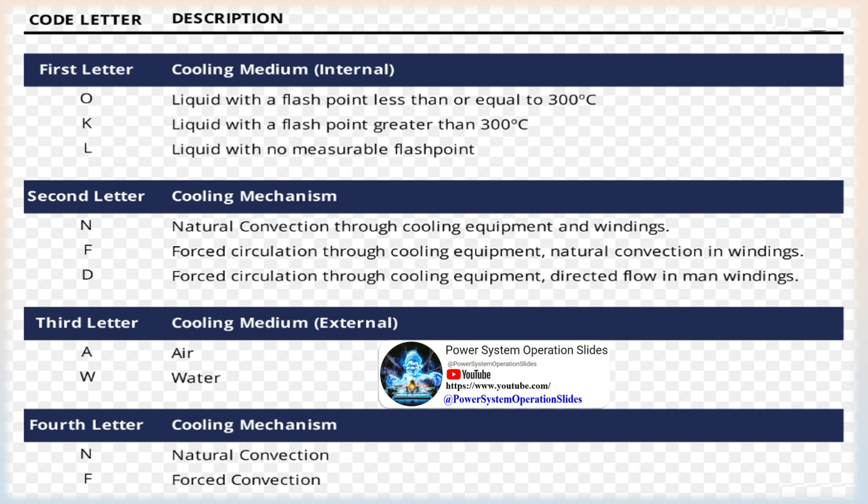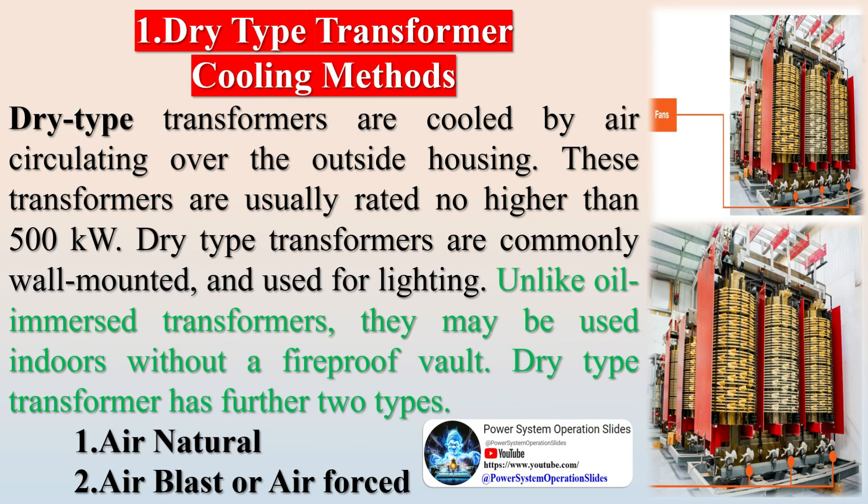Air Natural (AN) cooling is used in dry type, self-cooled transformers. In this method, the natural circulation of surrounding air is used for cooling the transformer. The windings of the transformer are protected against mechanical damage by a sheet metal enclosure. Air Natural cooling is used for low voltage, small transformers up to a few kVA.